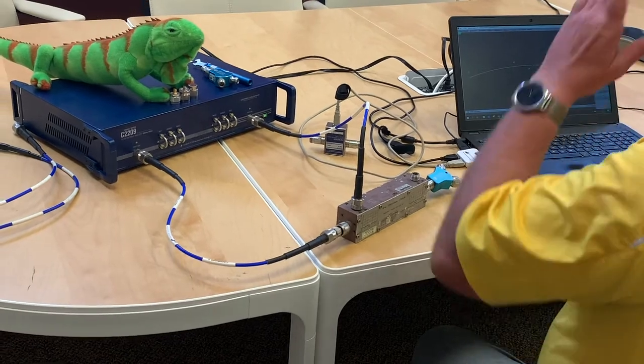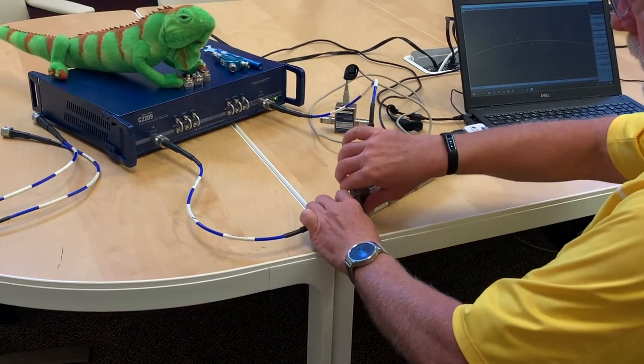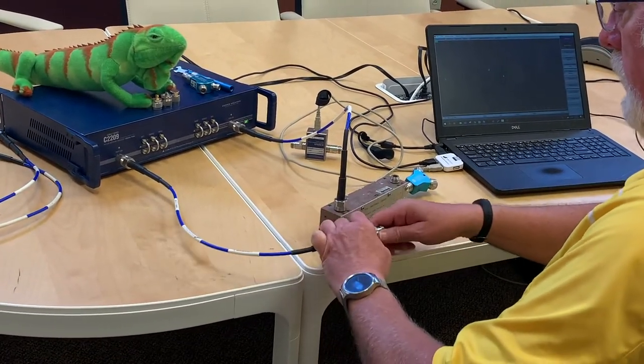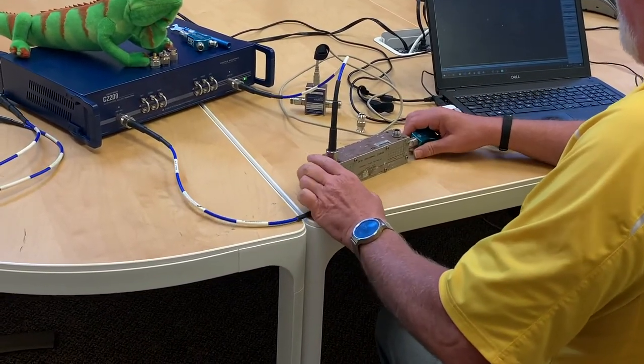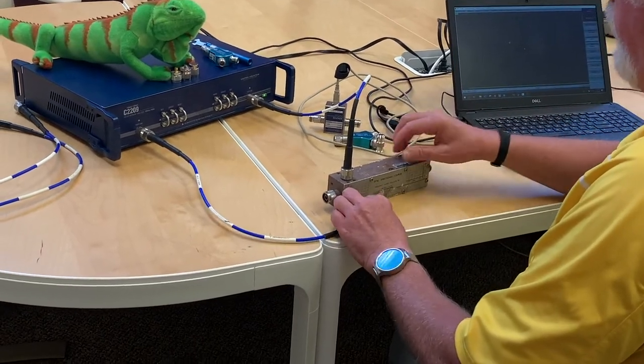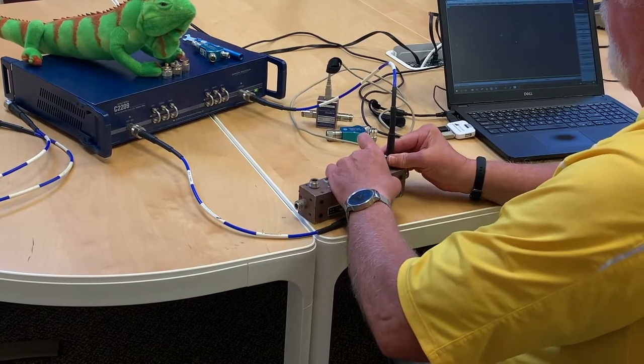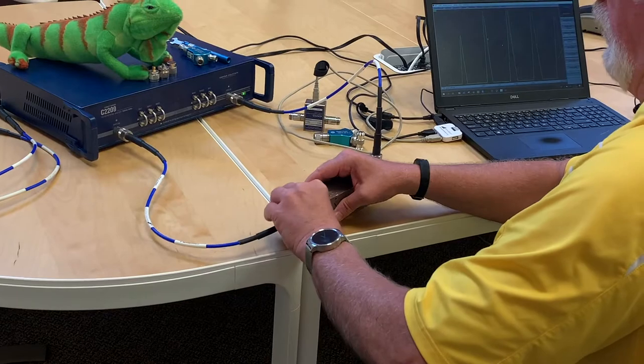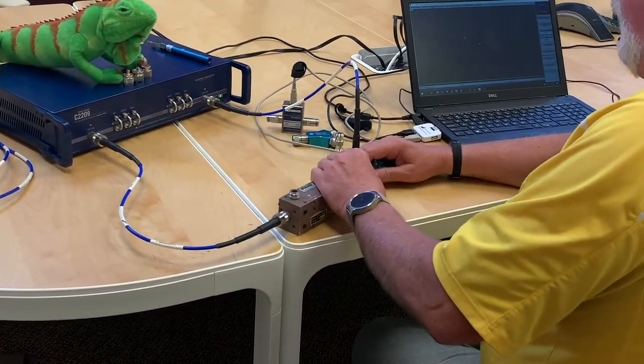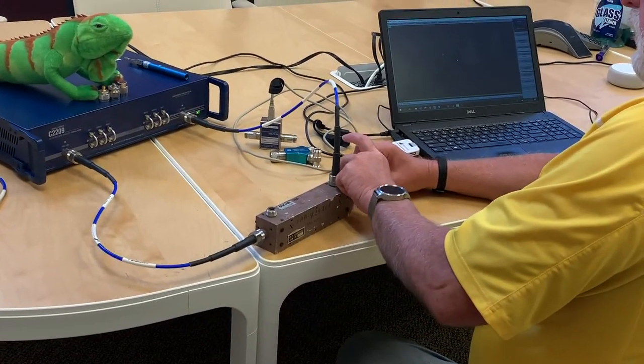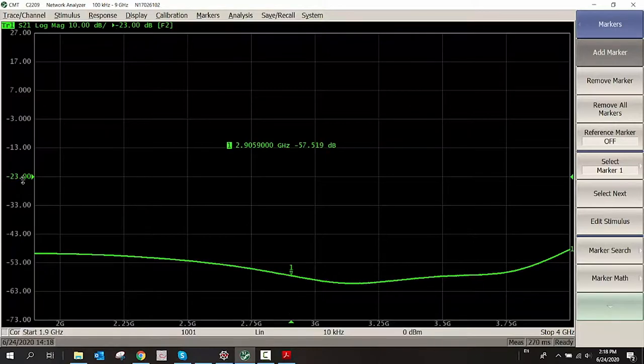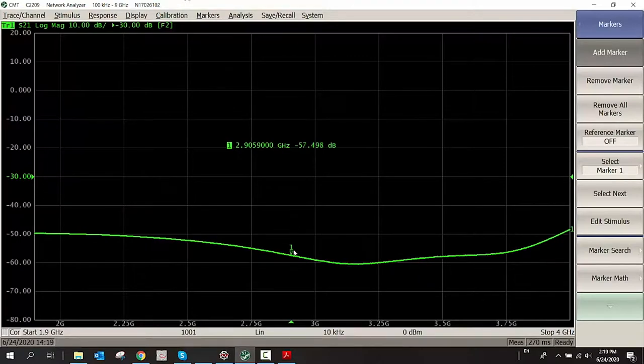And now let's look at the directivity. Theoretically, if I turn this coupler around and feed it, I should not see any signal on this port. But we will see one. And that's a small error, but it's important to know what it is. That will be the raw directivity of my bridge. And I need to load the output here.